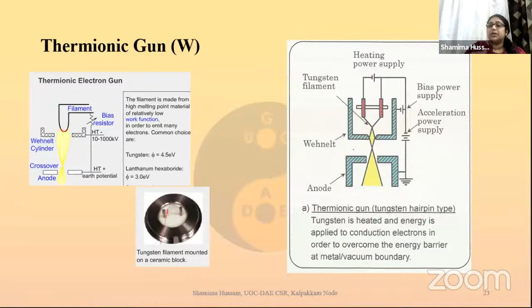We would heat the filament that we were using, whether it is tungsten or whatever, and then the same way we would give a bias to the Wehnelt cup, and we would have the anode plate, give another bias to it, and pull down the electrons. Just an important part is that these used to have this hairpin. Okay, this V point was very important. And what kind of material were we using here? Materials which had very low work function, so that we could heat them faster, and low work function means electrons could be emitted pretty fast.